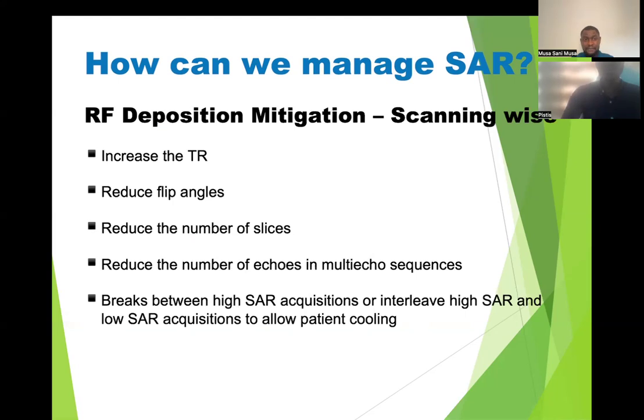How can we manage SAR? Increase your TR if possible, reduce your flip angle, reduce the number of slices, reduce the number of echoes, take breaks between high SAR acquisitions. So taking breaks now, someone might be wondering, why would I take a break between scanning one sequence and the other? It's like, for example in football, when it's extreme weather like 40 something degrees, they tend to have a cooling break. So it's the same thing here.